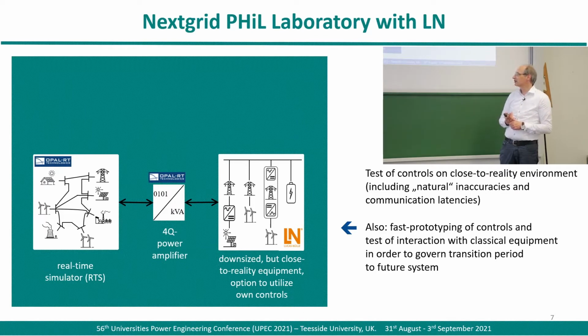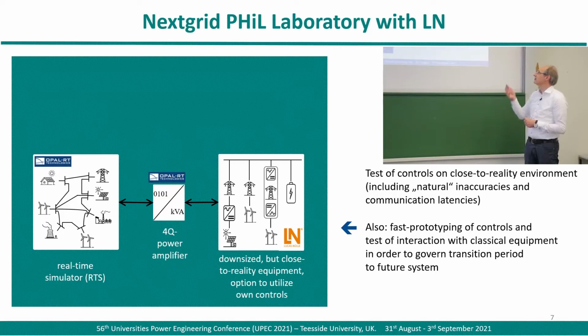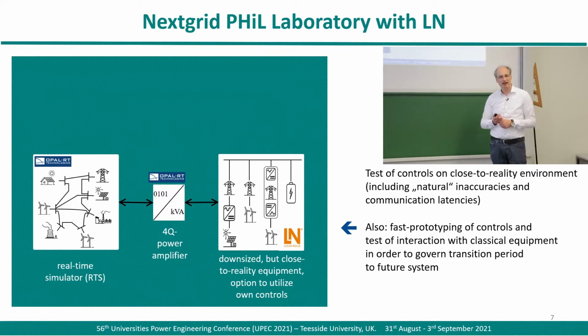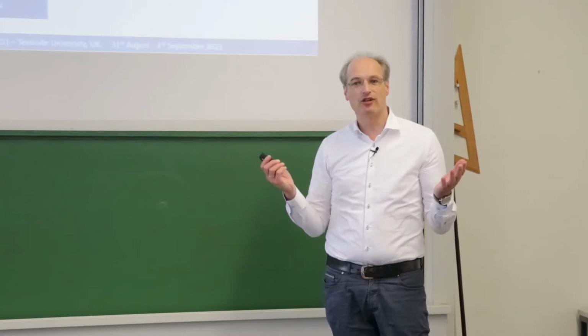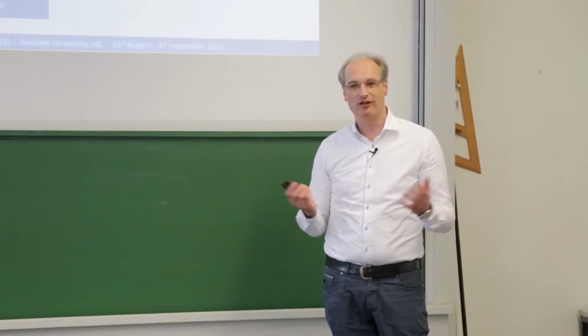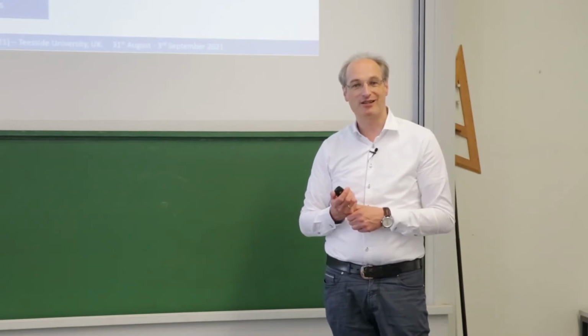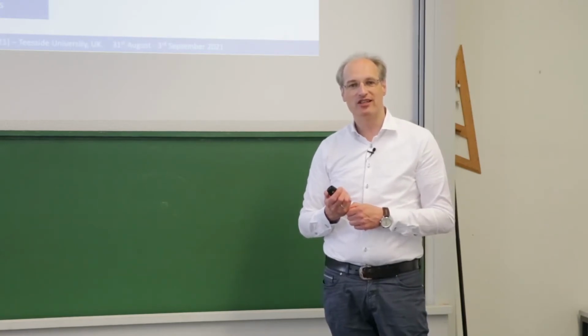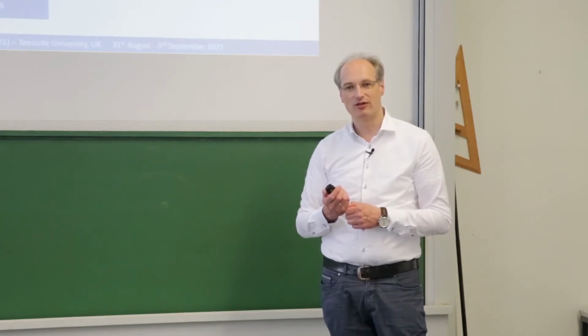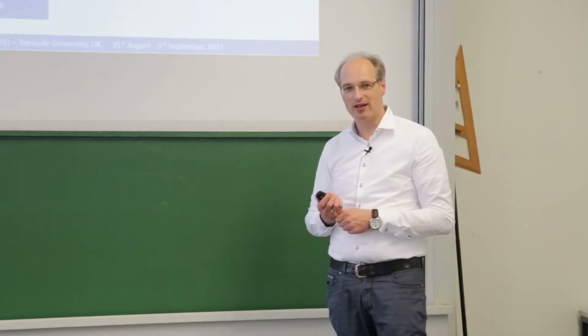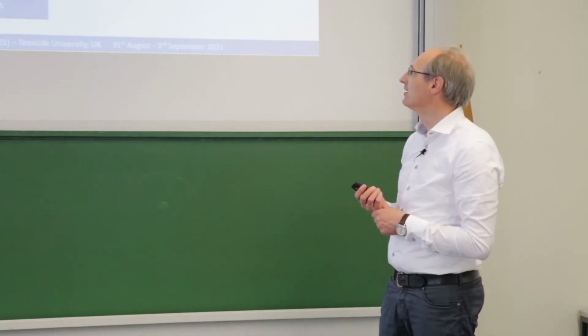In between, of course, we need a 4-quadrant power amplifier. This enables us to test the controls of close to reality environment. Of course, you could say we could simulate everything, including all of the grid forming controls, and that is what we are doing in development as well. However, we see a great benefit in doing this in the laboratory as well, since then automatically we will be faced with natural inaccuracies of measurement and communication latencies, which are taken into account and which in the end give more reliability and trust to our results.